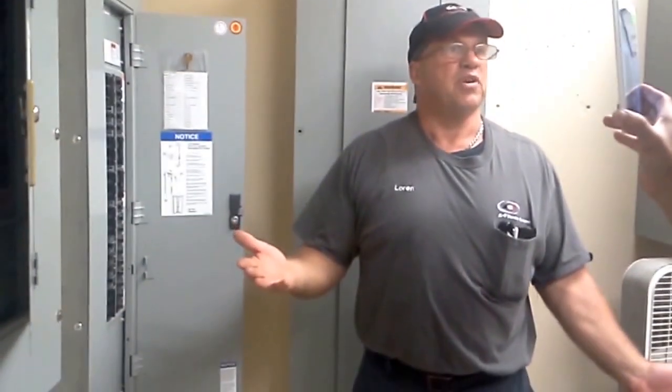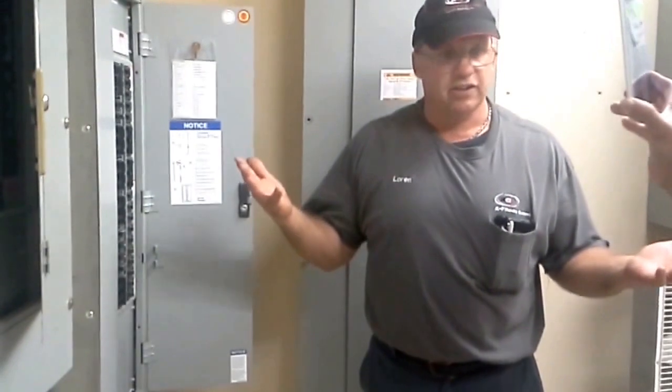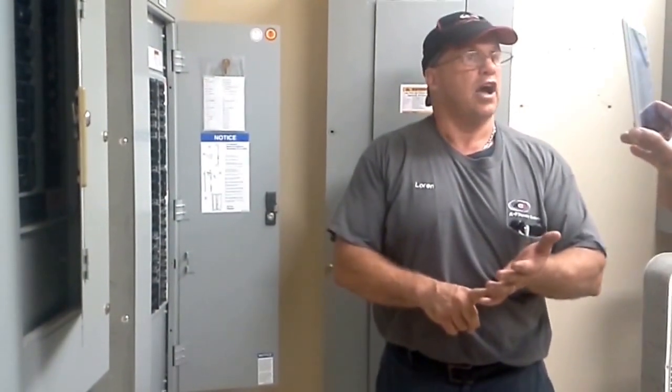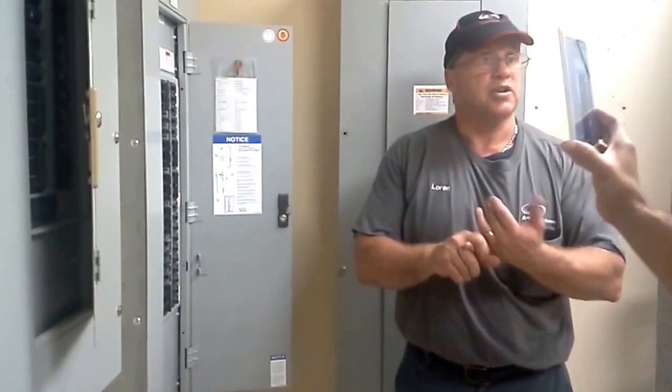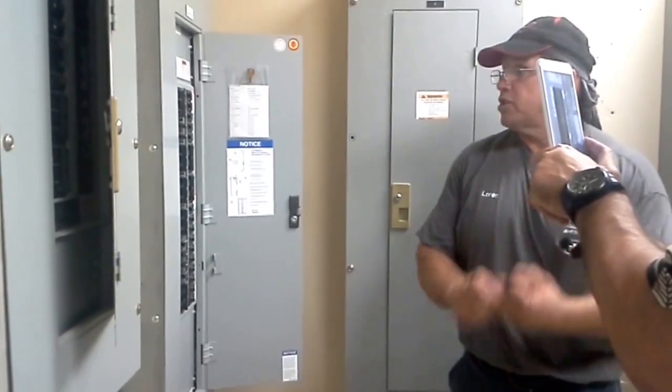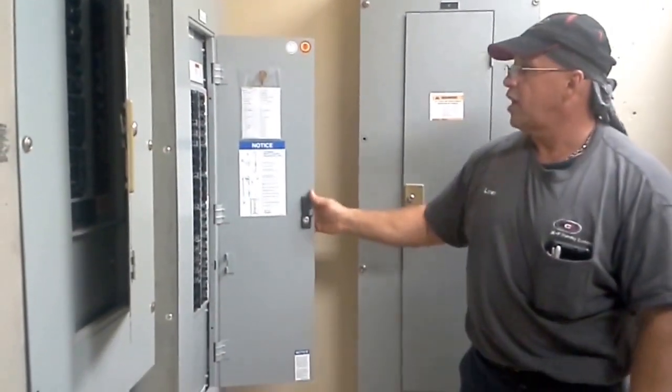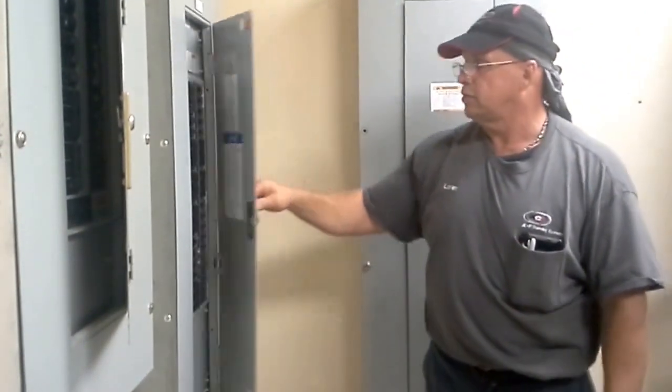So 3-4 weeks go by, I didn't hear the alarm go off, and that's why. I didn't hear the generator because you've got a dead battery. Now you not only have a dead battery, you have a bad battery on start, because you're not going to be able to recharge that battery again. That's the purpose of 2 circuits. Not required, but highly suggested.